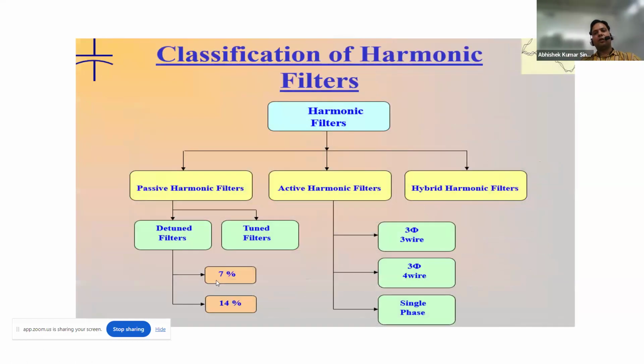Now, classification of harmonic filters. Harmonic filters can be classified into multiple types: the detuned filter, the tuned filter, the active harmonic filter, and the hybrid harmonic filter. So what is a detuned filter? A detuned filter comes in two types, one is 7% and another is 14%. We will discuss both of these, what 7% and 14% are and what they are used for. And one is the tuned filter.